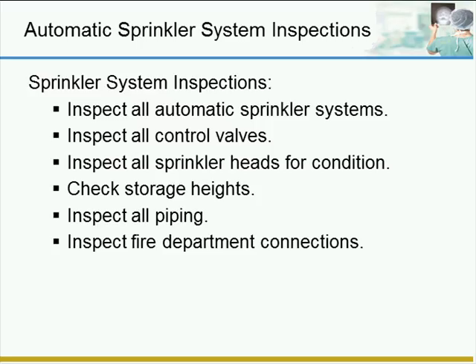You should also be able to inspect your fire department connections. These are pipes that extend through the exterior wall of the building where the fire department could come and pipe in or pump in auxiliary water from their trucks or from hydrants. These should have tightly secured caps on them to prevent children or vandals from placing objects, such as soda cans, into these connections, rendering them inoperative.